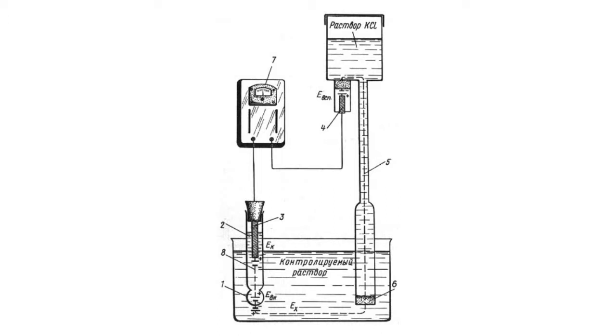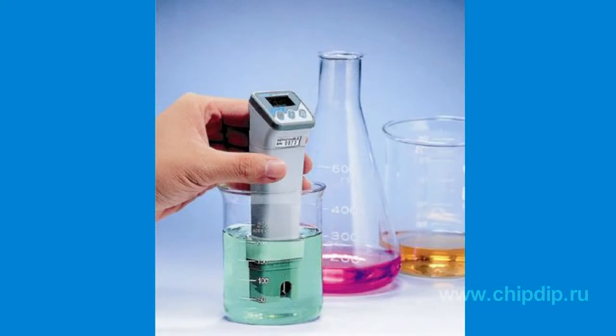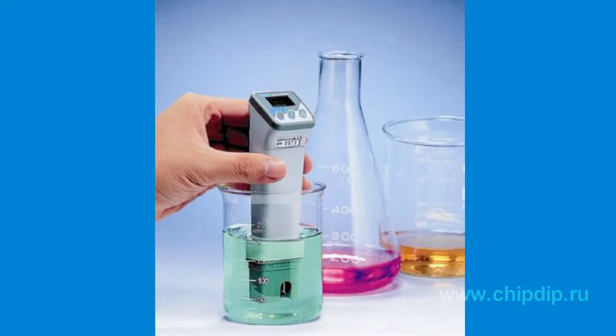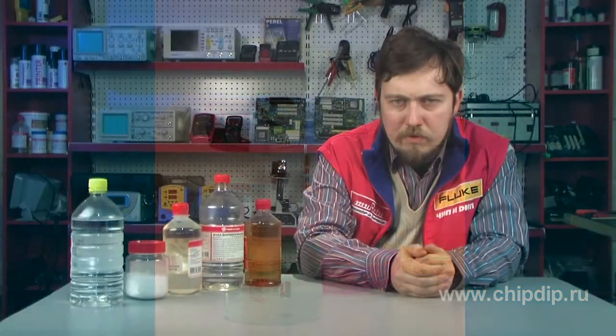Since the EMF depends on the pH of the solution, the device scale is graded in pH units. This is the most accurate and universal method for pH measurements, well suited for cloudy and colored solutions.